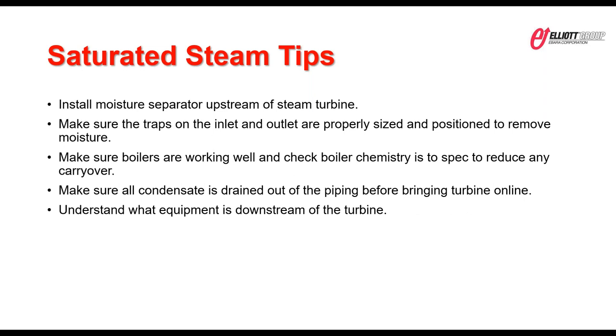Understanding what's downstream of that. So if you have saturated steam and you're going to run a back pressure turbine, there's going to be moisture present in the exhaust. So now how does that affect what's downstream of that? Things like heat exchangers, probably it doesn't make a difference, but what if there's other process equipment downstream, other turbines or things like that, where now you have to do something downstream to make sure that at least the steam there is dry. So, just understanding how moisture may affect those downstream components as well.